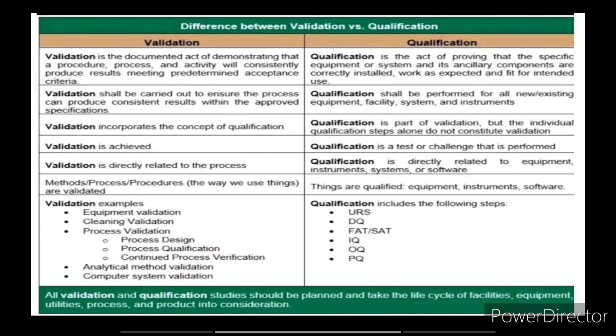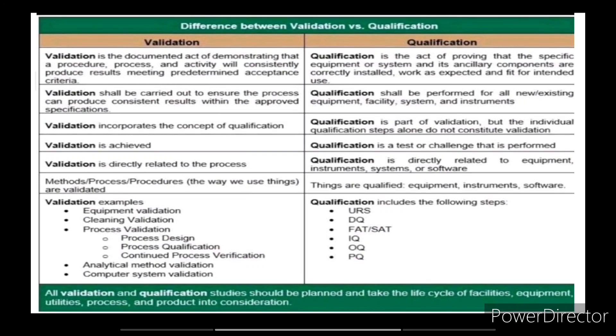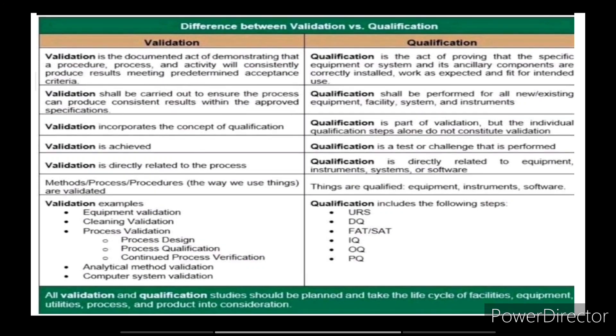So what is the difference between validation and qualification? Validation is the documented act of demonstrating that a procedure, process, and activity will consistently produce results meeting predetermined acceptance criteria. Qualification is the act of proving that specific equipment or system and its ancillary components are correctly installed, work as expected, and are fit for intended use.